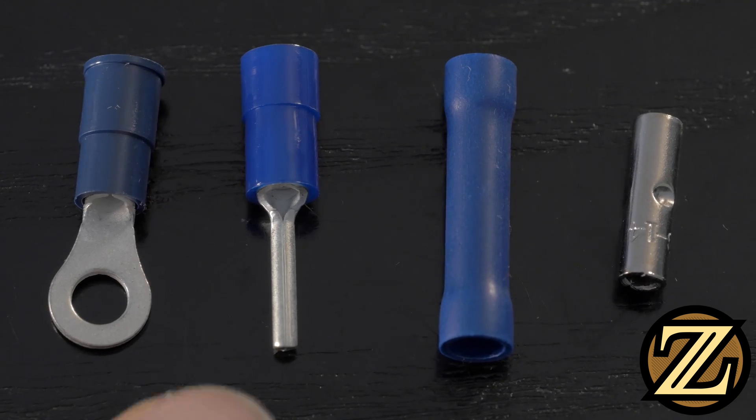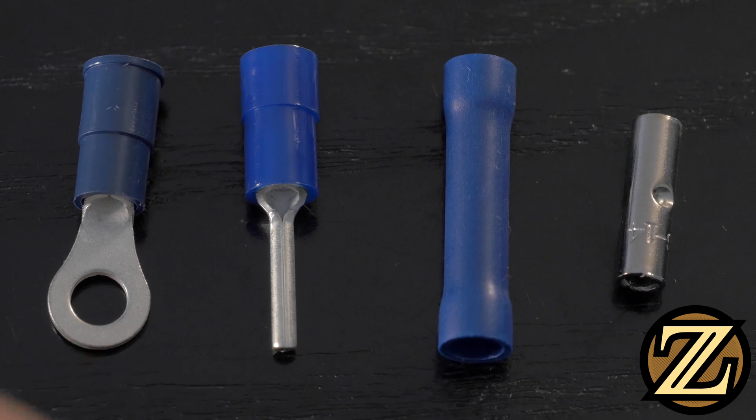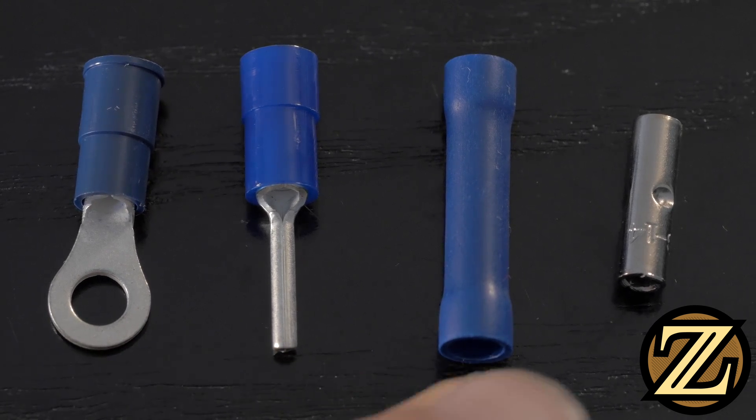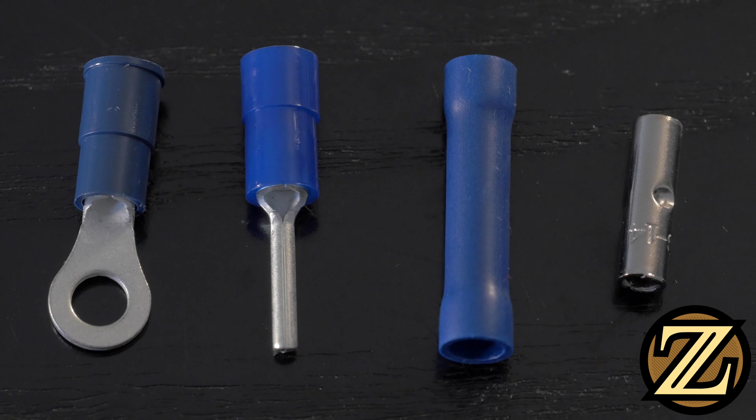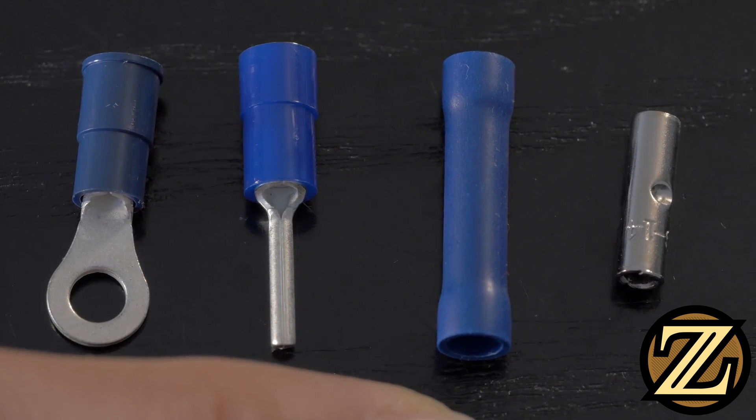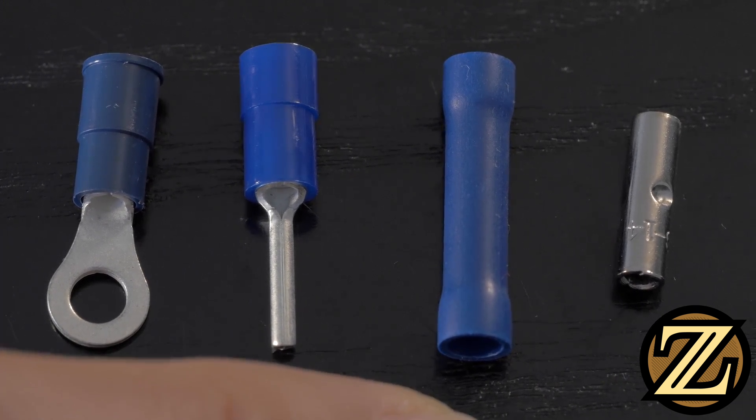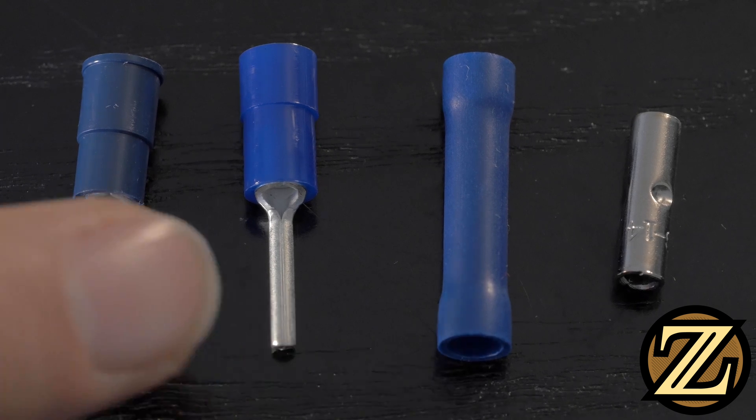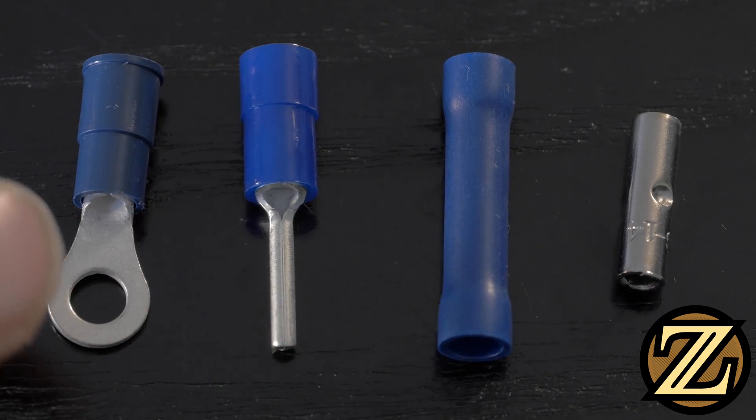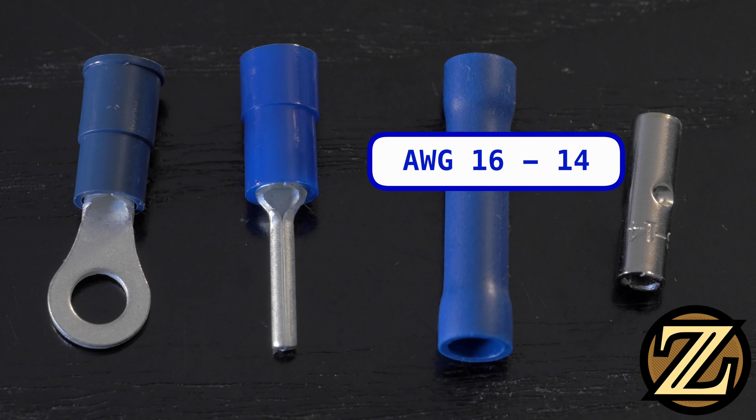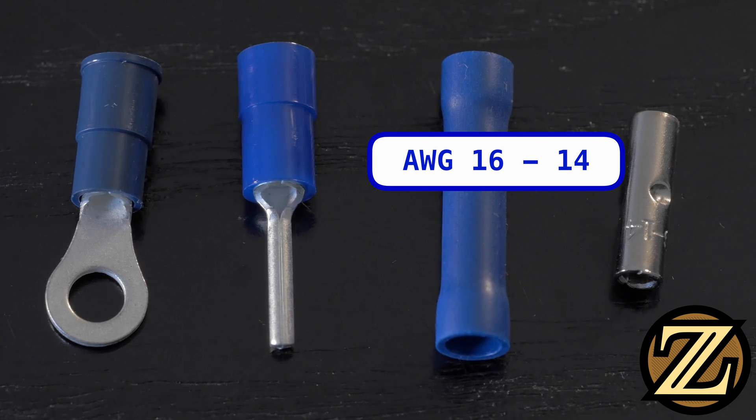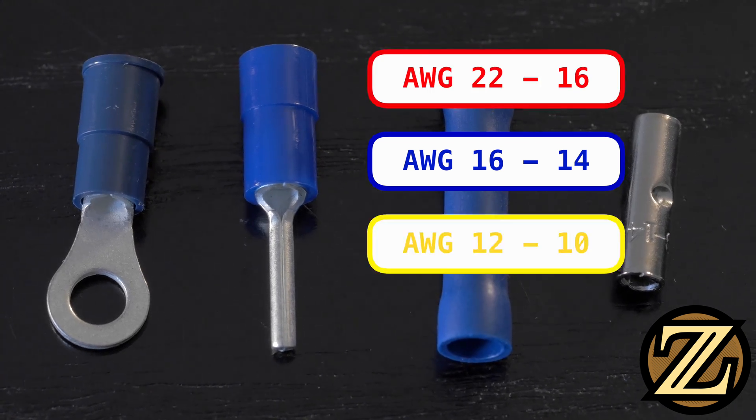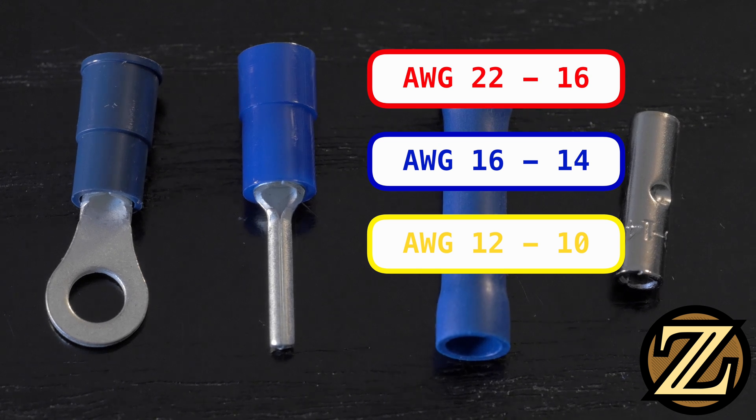Here we have four different crimp devices: a pin terminal, a ring terminal, an insulated butt splice, and an uninsulated butt splice. Notice how on all the insulated devices we see blue shielding. There's a reason for this, and it's to denote what size wire these devices are rated for. Blue is good for gauges 16 through 14, red is good for gauges 22 to 16, and yellow is good for gauges 12 to 10.